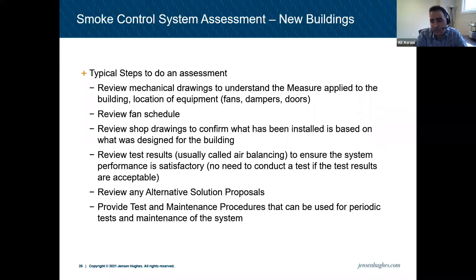And as part of that, you can confirm some of the information that you're looking for. So we're looking at the information and see, okay, this matches. They tested the fan and the performance shows it's 9,900 something CFM. It's pretty close to 10,000. We don't expect it to be exactly 10,000, right? So it matches and it works. So basically the system was designed properly, and if you see that result and you confirm that result, there's no need to conduct a test again.